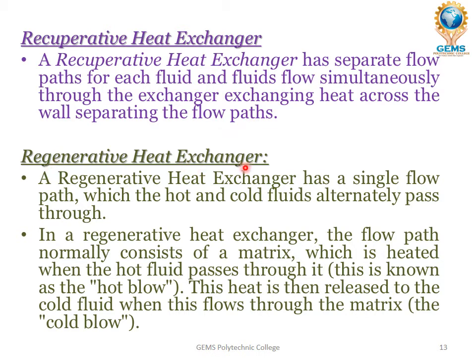And regenerative heat exchangers. A regenerative heat exchanger has a single flow path through which the hot and cold fluids alternately pass. In a regenerative heat exchanger, the flow path normally consists of a matrix which is heated when the hot fluid passes through it. This is known as the hot blow. This heat is then released to the cold fluid when it flows through the matrix, and this is called the cold blow.